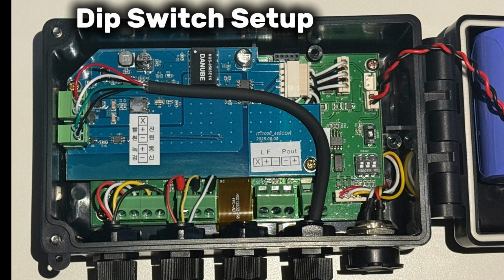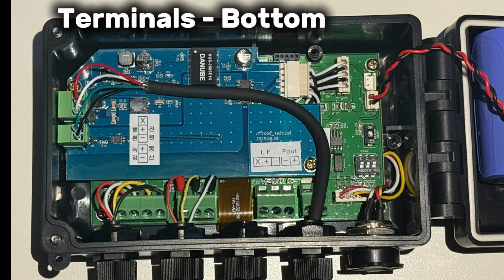Below the communication board is a dip switch with 3 small switches. You can set the device ID from 1 to 99 by adjusting these. Please refer to the ID table in the manual for the correct setup. Let's look at the terminals at the bottom.